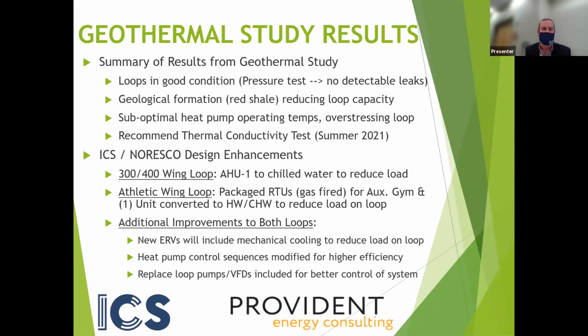In the athletic wing, specifically the auxiliary gym, those units are going to be converted to gas-fired units and basically DX cooling, which means that they don't rely on the heat pump loop, the geothermal loops. So those are some of the measures that we're doing to reduce the load.